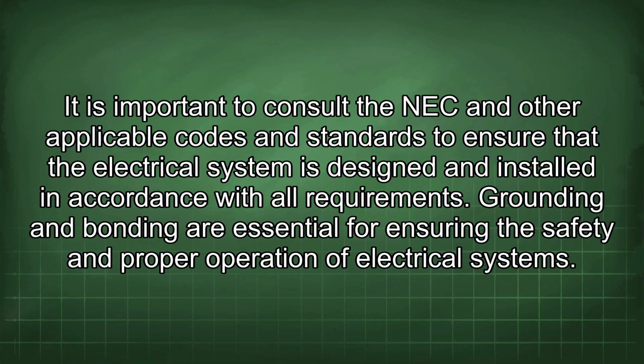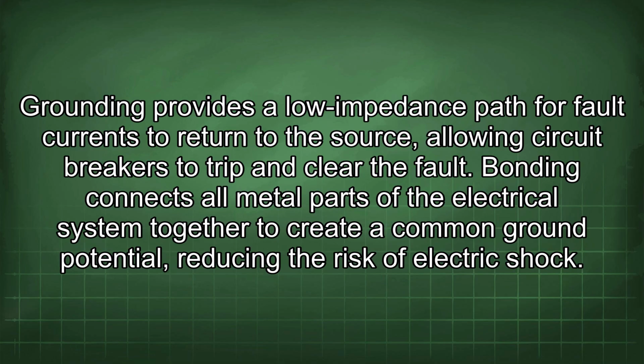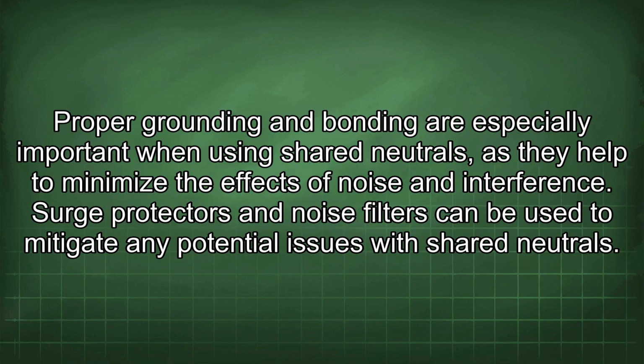Grounding and bonding are essential for ensuring the safety and proper operation of electrical systems. Grounding provides a low impedance path for fault currents to return to the source, allowing circuit breakers to trip and clear the fault. Bonding connects all metal parts of the electrical system together to create a common ground potential, reducing the risk of electric shock. Proper grounding and bonding are especially important when using shared neutrals, as they help to minimize the effects of noise and interference. Surge protectors and noise filters can be used to mitigate any potential issues with shared neutrals.